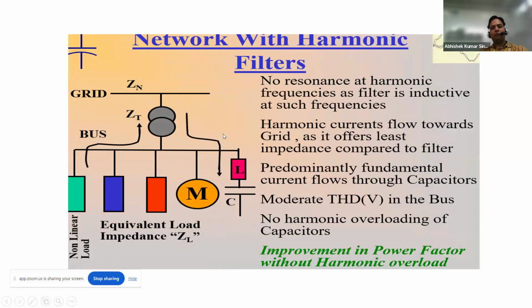So in a network with harmonics, if there is a non-linear load, what will happen? The harmonic is there, and the harmonic will trend to the supply. It will not come here. Why will it not come here? Because we have placed a reactor here. If it is not there, then what will happen? Current will flow like this and go into the capacitor, because it is the least resistive path for it. But we have an inductor, a reactor, so it will not come into this.